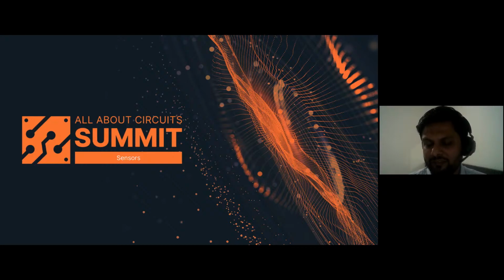That's a good question. When talking about the differential pressure sensor with its thin membrane, even at higher altitudes, when two ports are open to the air, you don't need any compensation for those systems, because they are like an open system, and when you put them inside your application they become a closed loop. So for those applications, the environment doesn't play a role. For absolute pressure sensors, which are like barometric pressure sensors, the range is around 300 hectopascal or 300 millibar to 1300 millibar, which is quite wide. So for the differential pressure sensors that we have, we don't have to compensate those values. But in the end application, even if it's not a closed system, you might have to compensate through the host controller. Otherwise there is no requirement.